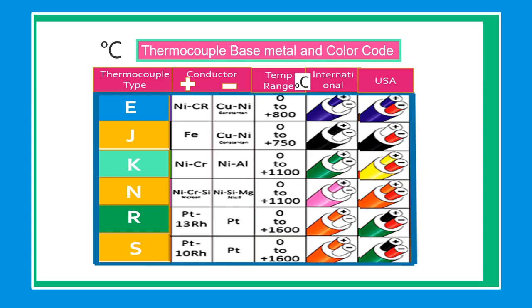For color code chart, refer at the chart for your reference. The temperature range in type E in degrees Celsius are 0 to 800 degrees. In type J, 0 to 750 degrees. In type K, 0 to 1100 degrees. In type N, 0 to 1100 degrees. And type R, 0 to 1600 degrees Celsius.